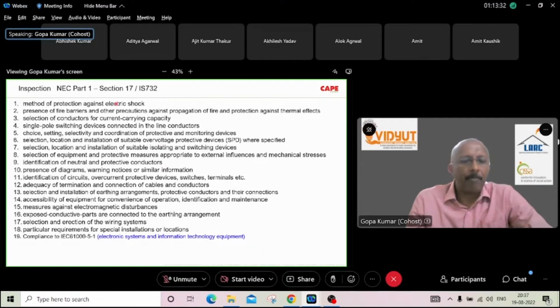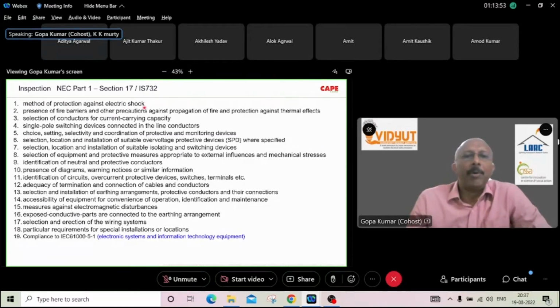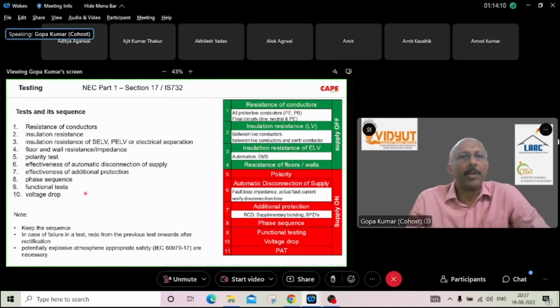As I said, with a properly designed, erected and tested electrical installation, the chance of an accident is almost nil. Now, what is this testing? Testing consists of 2 parts. Inspection consists of almost 19 points, starting with the method of protection against electric shock, because there are several methods which can be applied in an industry or in a building. So the appropriate safety measures shall be implemented, and the inspector has to verify whether these are correct or not. Similarly, there are several inspection points, the physical inspection, then the testing.